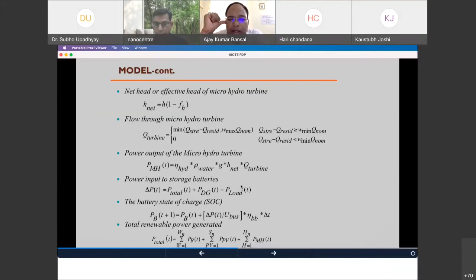Then we will calculate the power input to the storage battery. That will be the total power generated by the renewable energy sources plus the total power generated by the DG system, subtracted from the load requirement of the system, and on that basis we will charge or discharge the system. So delta P will be positive if we have more generation than load, meaning the battery will be charged; otherwise the power input to the storage battery will be negative, meaning the battery will be discharging because the load is more and generation is less.